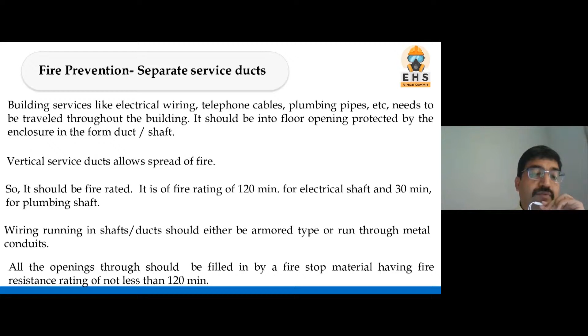Now, what does it mean? Just imagine there is a building, various floors are there, and the electrical installation or electrical wiring is going through the entire building, there will be an opening at each floor level. Now, if that opening is not properly sealed, then what will happen? The fire may be at the ground floor, but the smoke may be at the topmost floor. And it is very difficult then to understand the origin of the fire. So we cannot attack the fire. So fire may spread. That's why it is very clearly mentioned that it should be sealed at every floor level. This is very important from a fire point of view.